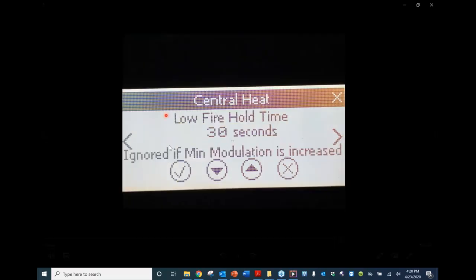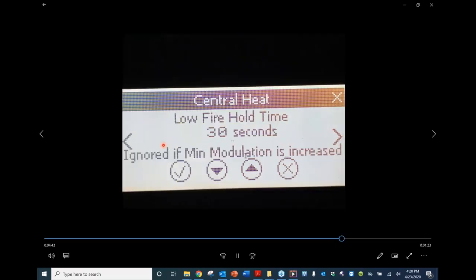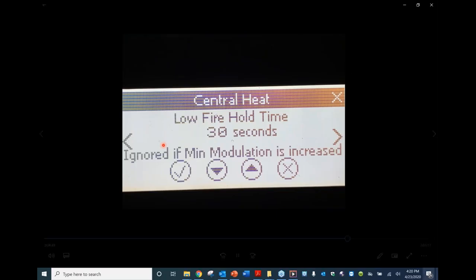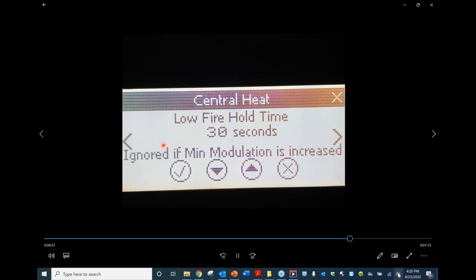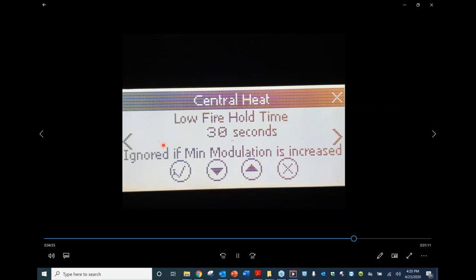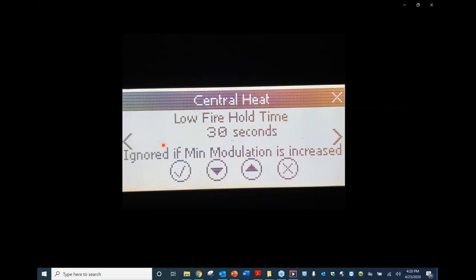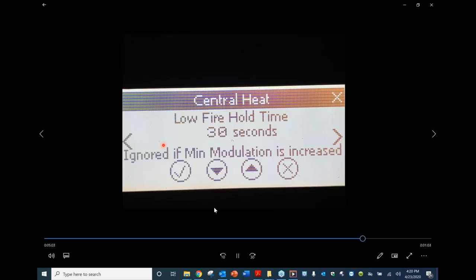Our low fire hold time. Now this is going to be a very important setting. Low fire hold allows the boiler to see what's going on in the system before releasing and ramping up the burner. If it ramps up too quickly, it can result in short cycling. We really don't want these units short cycling. Short cycling causes early component failure and makes them less efficient.